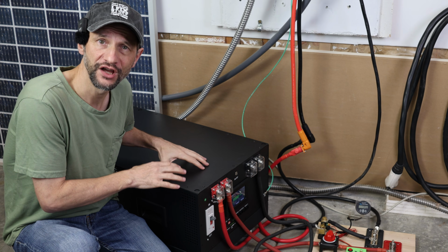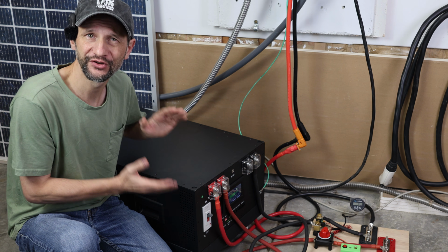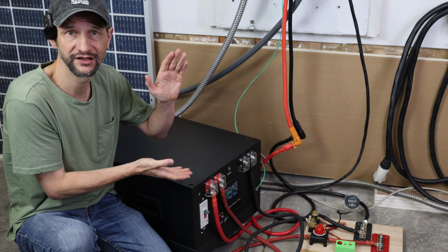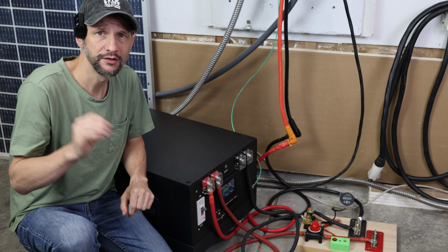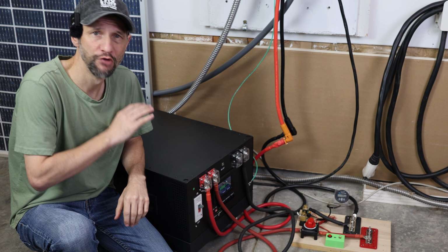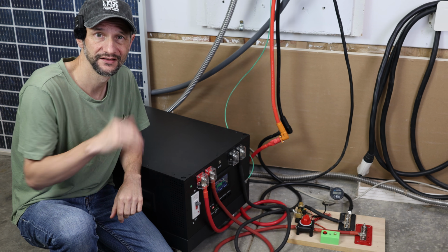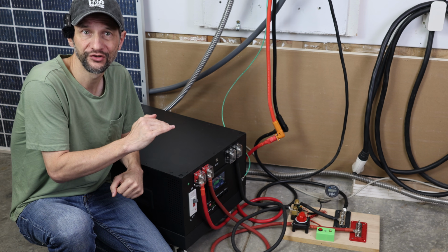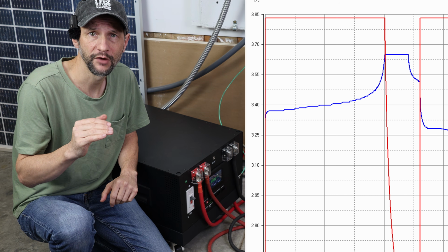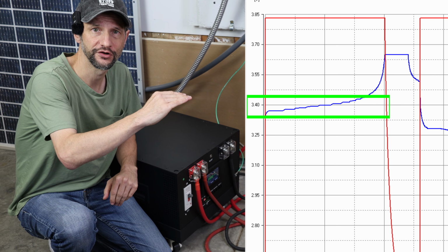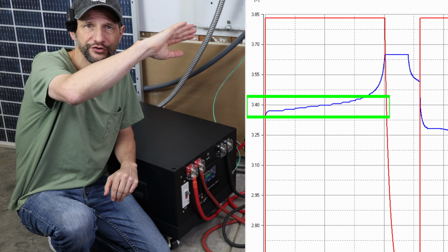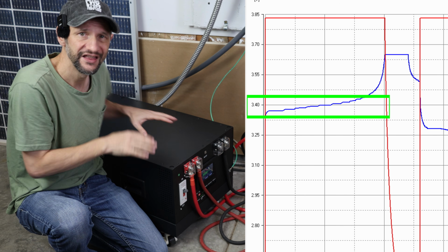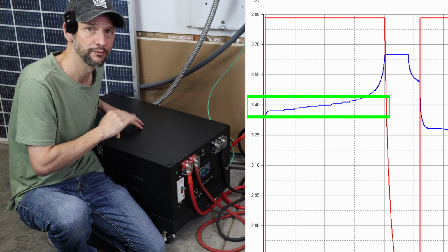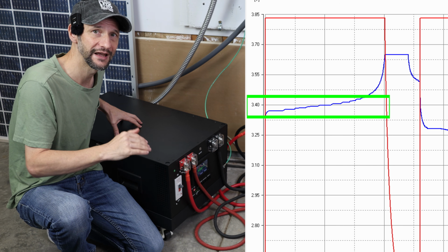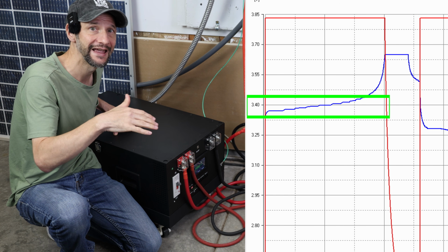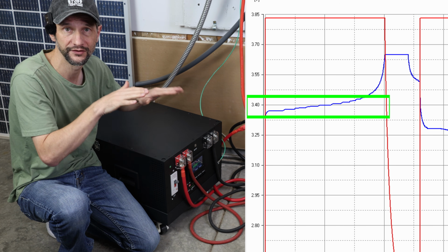You might be concerned about not using the full capacity of the battery, but there's actually very little capacity at the tail end of the charging curve. I think you'll see when we run the test that we're able to use most of the battery capacity with these settings. And you might think, well, if lower's better, why not reduce the charge voltage even more? The problem is lithium iron phosphate has a very flat charge curve. And if you don't get above that flat line portion of the curve, the cells will never balance. And then you'll have one cell constantly getting stressed more than the others. So it's very important to have a high enough charge voltage and to hit that on a regular basis so the cells can balance out.